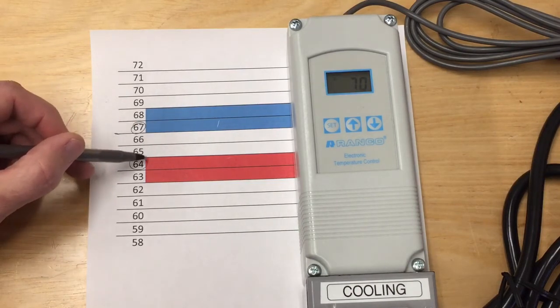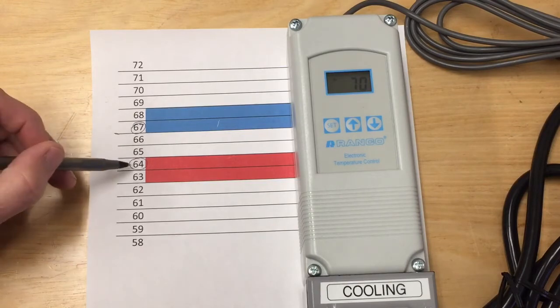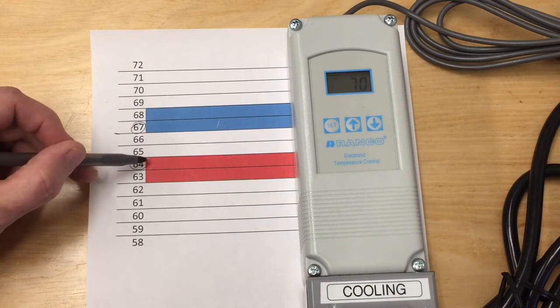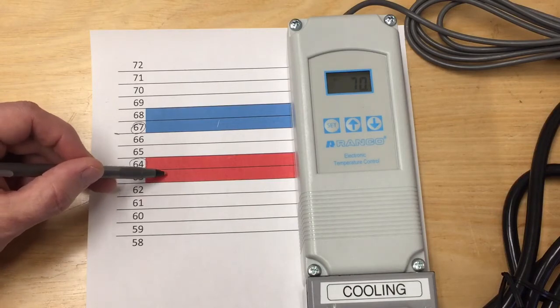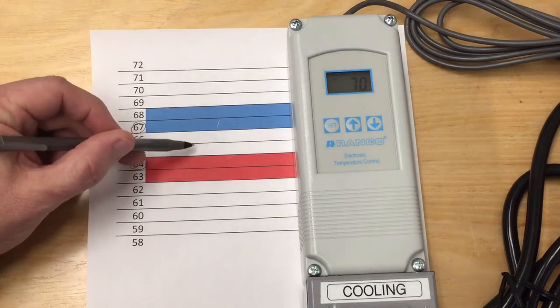Now if the temperature drops, I set 64 degrees on the heating side with a two-degree differential, so it'll go as low as 62 and the heater will turn back on, keeping me in this band as well.